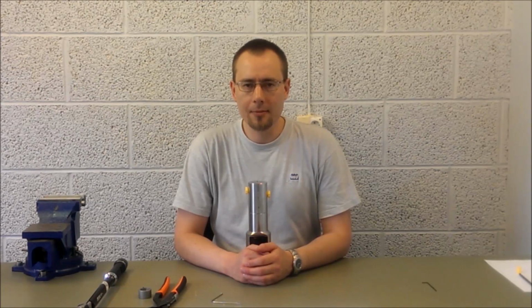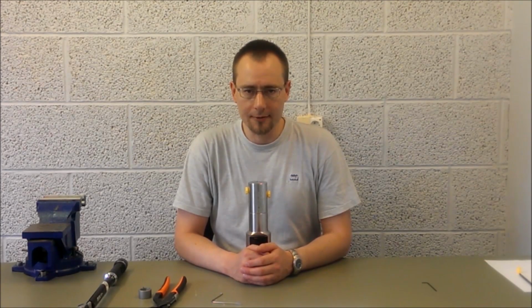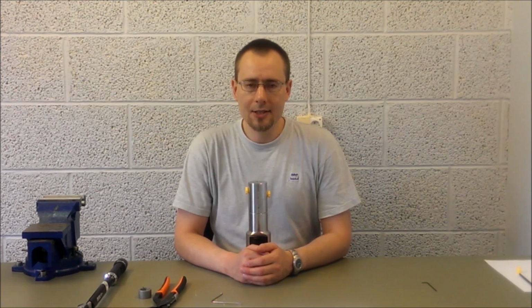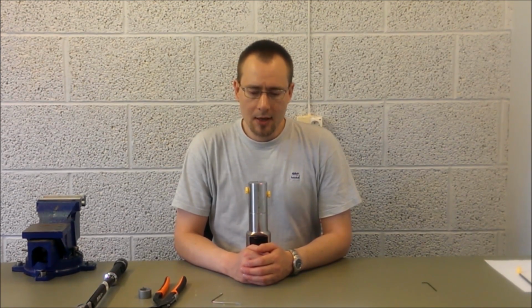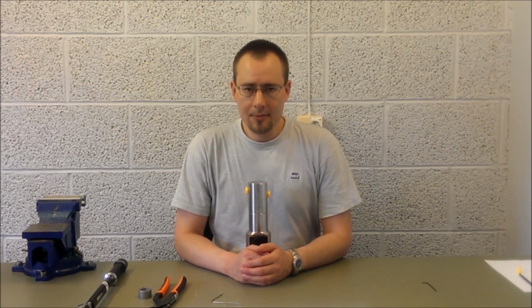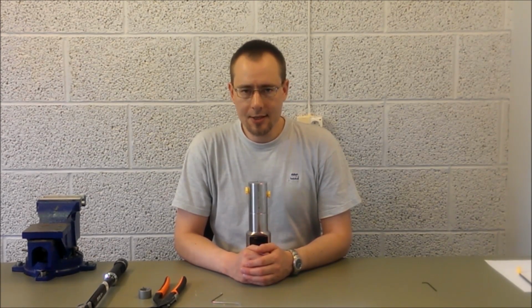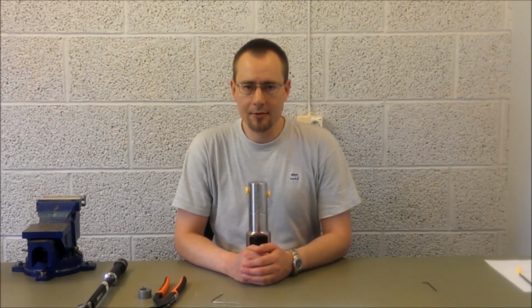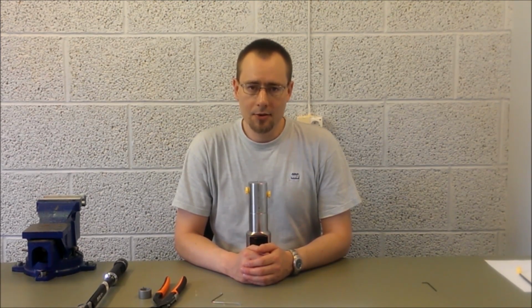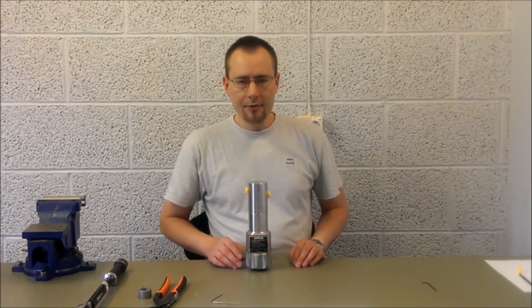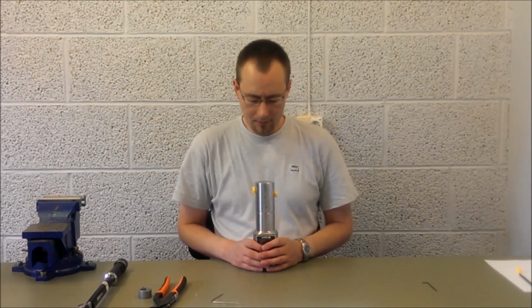Now we will go through the procedure for changing of the dump valve. Make sure that the system is depressurized and that valves upstream and downstream are closed. This is necessary because you have to dismantle the regulator from the system to do the changing of the dump valve. Now we have the regulator dismantled from the system. We hold it like this, the adjustment wheel down, keep it in a straight line, and unscrew the housing.